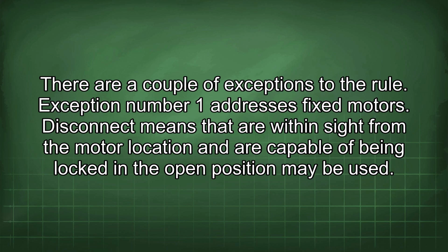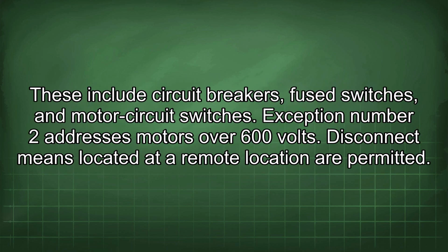Exception number 1 addresses fixed motors. Disconnect means that are within sight from the motor location and are capable of being locked in the open position may be used. These include circuit breakers, fuse switches, and motor circuit switches. Exception number 2 addresses motors over 600 volts. Disconnect means located at a remote location are permitted.